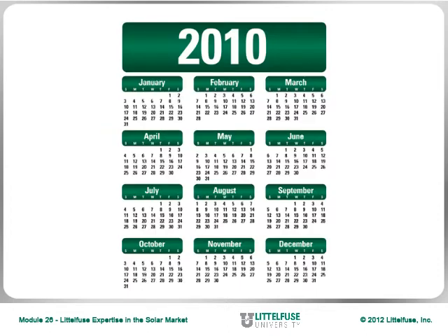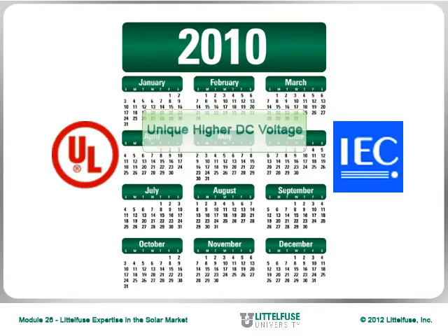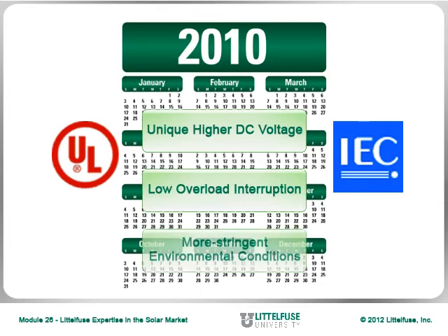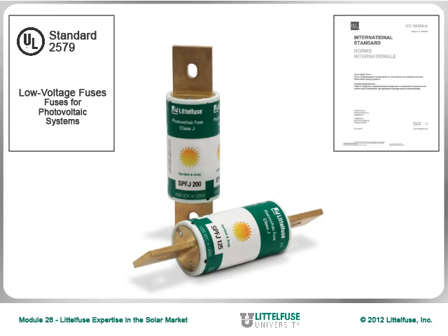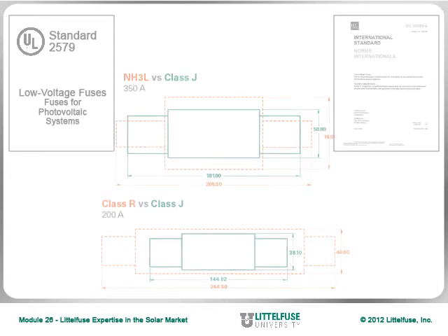In 2010, both organizations introduced new standards to address the protection needs of photovoltaic power systems. These standards address the unique higher DC voltage, low overload interruption, and more stringent environmental conditions that typical industrial circuit protection standards do not address. The SPFJ meets both UL-2579 and IEC 60269-6 standards, while providing a space-saving solution smaller than alternative 1000V DC fuses.